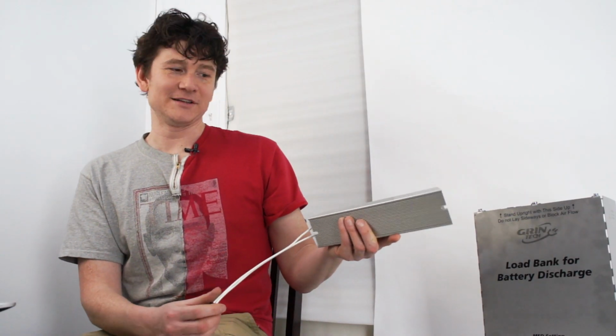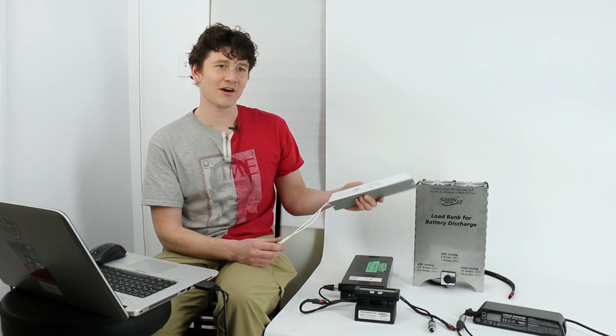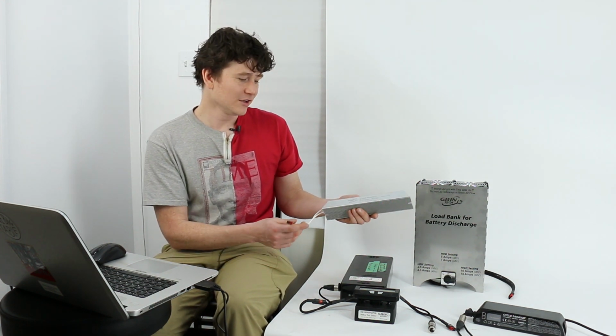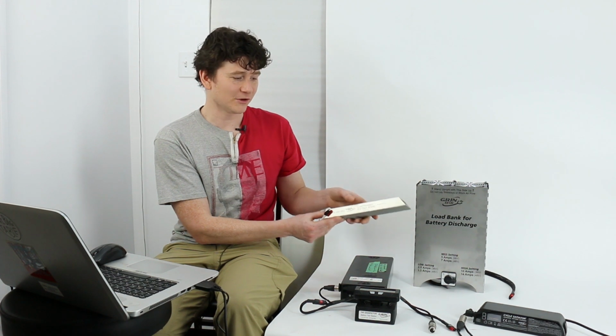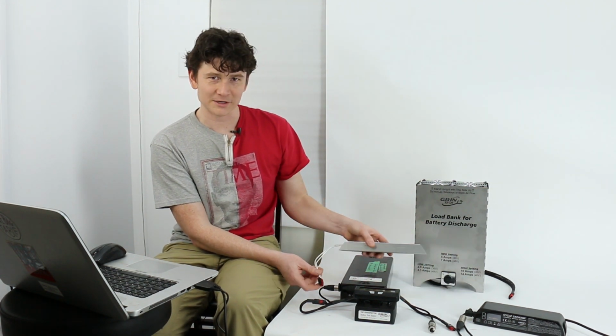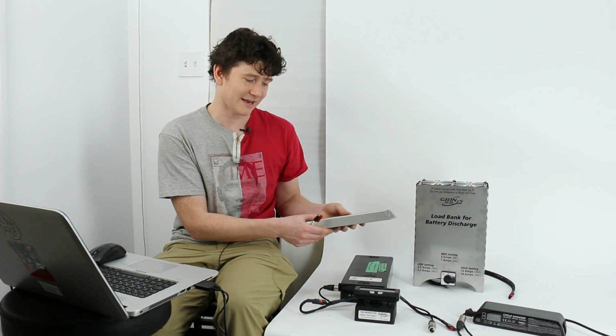One thing to note about a resistor like this: even though it's rated for 400 watts, it will get extremely hot during that discharge. If you have just a simple resistor, don't let it sit on a piece of paper or a wooden bench. Make sure it's mounted on an insulated, high-temperature surface, because it will get scalding hot to the touch even when used within its ratings.